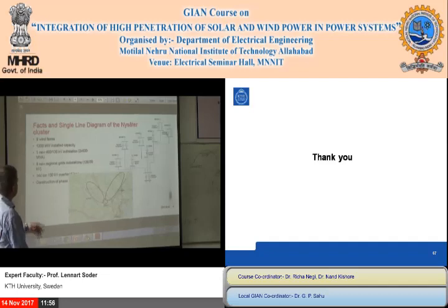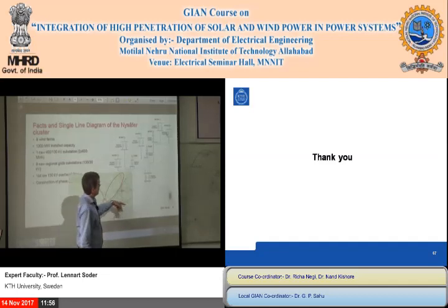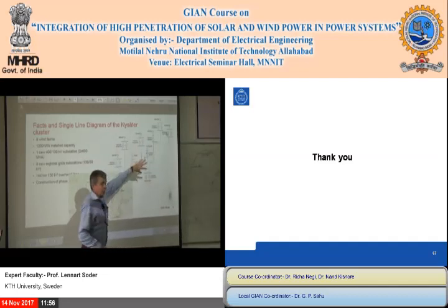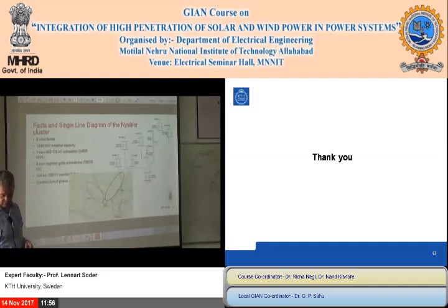And the idea is a wind farm with 1,200 megawatt of installed capacity, which is rather big. So they build a new transformer here, and the idea is that it will look like this: you have the 400 kV system here, and then we have two transformers in parallel, and then a 130 kV system, and then a grid out to all the wind farms. So it's mainly, you can call it, a collection grid from the wind farms.